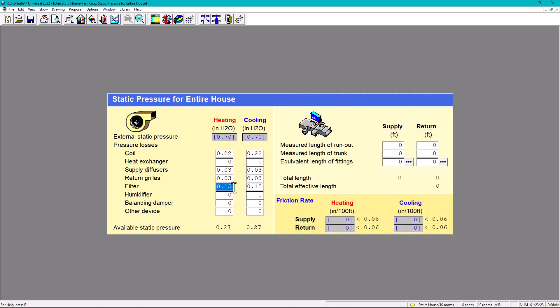So far, how much do we have available? We started with 0.70 inches of water column based on the blower. And then because of my losses so far, I have 0.27 available static pressure. We want to have more, but we still have to continue with the losses. We don't have a humidifier. For balancing damper, Manual D also suggests 0.03. So what happens now is that we have 0.24 inches of water column of static pressure.